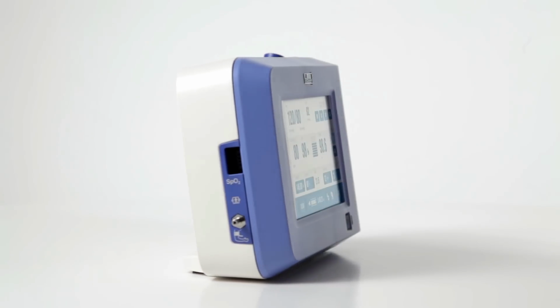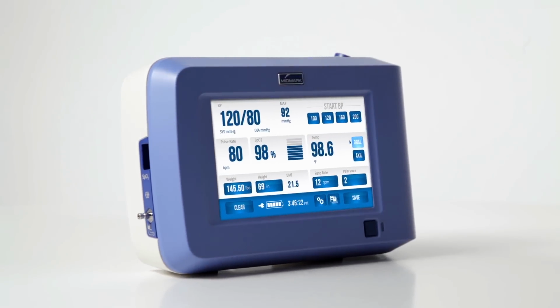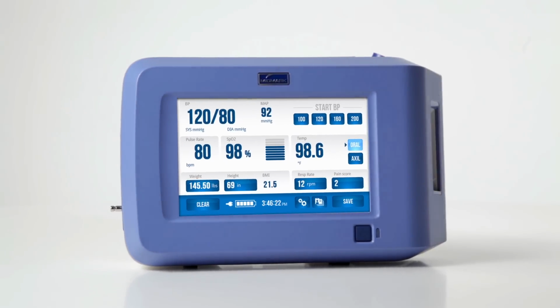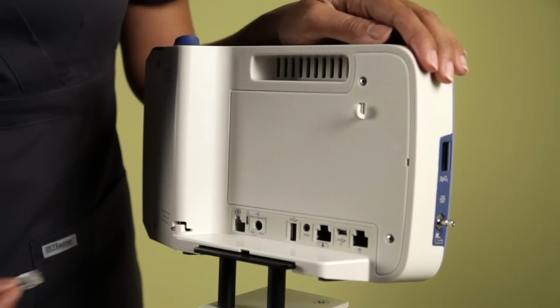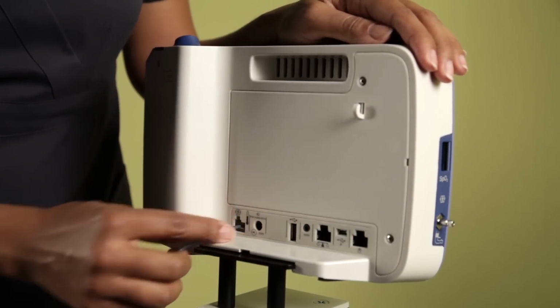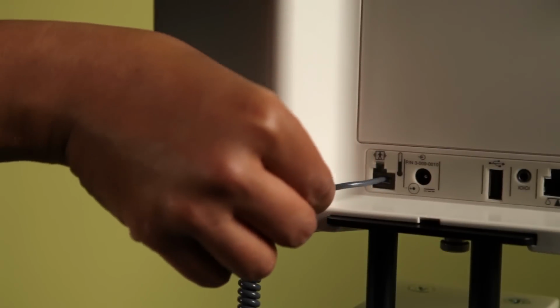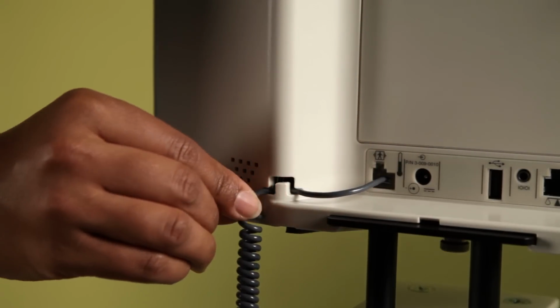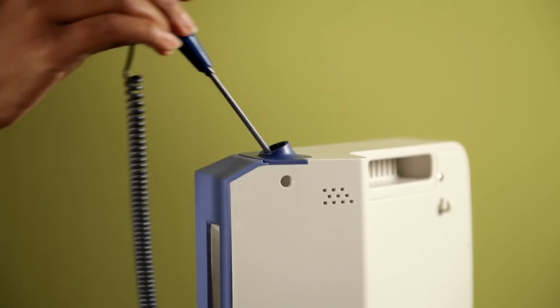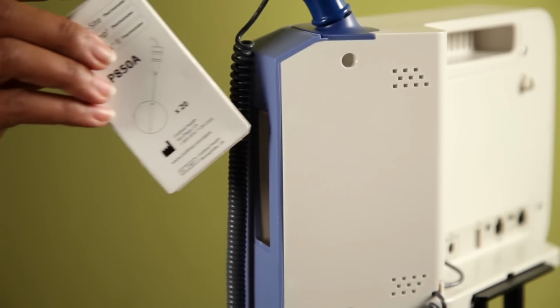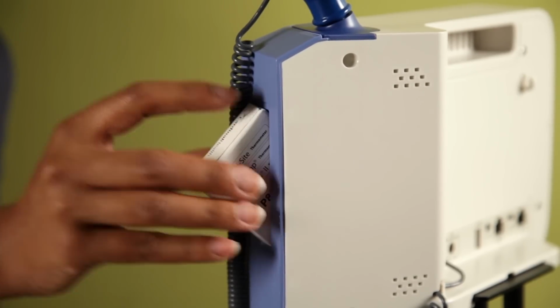Before attaching the power cord to the device and turning the power on, attach all accessories to the device. First, install the temperature probe to its connector, located on the back of the device. Thread the temperature probe cord through the temperature cord guide. Insert the temperature probe into its well and place the box of probe covers in the device probe cover holder.